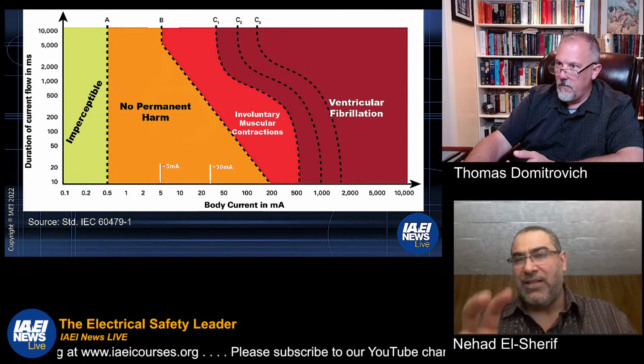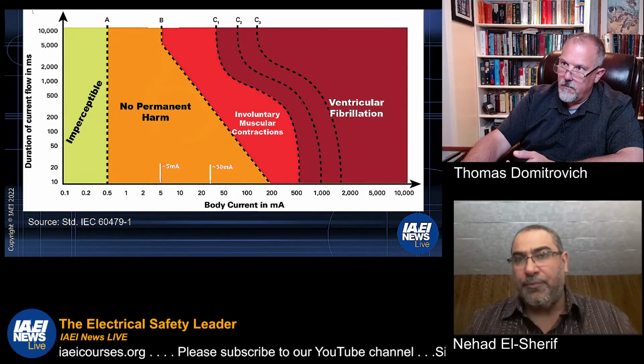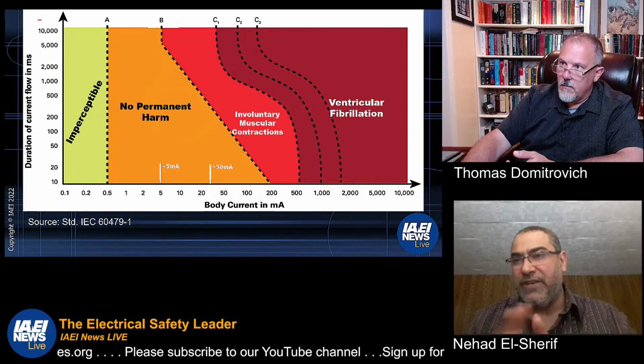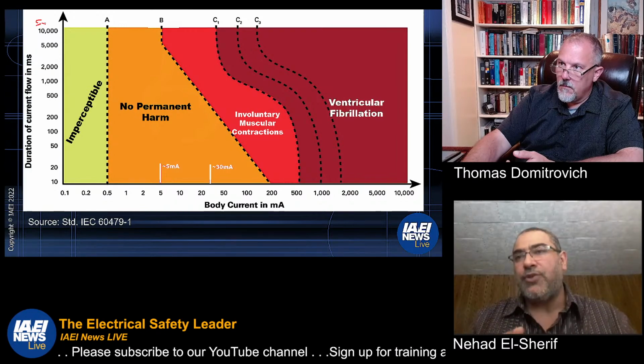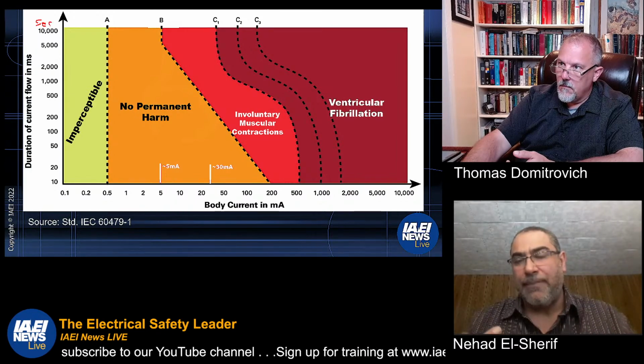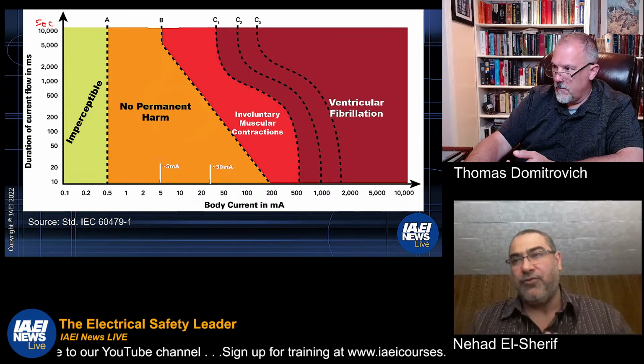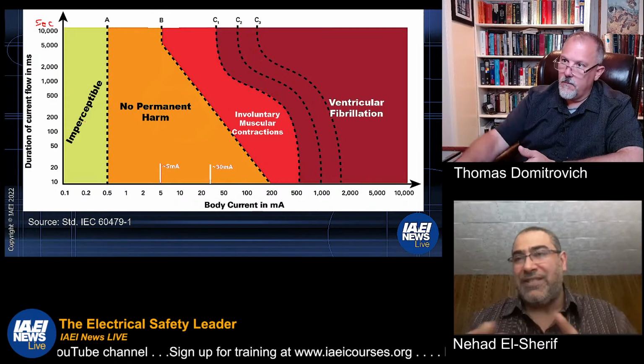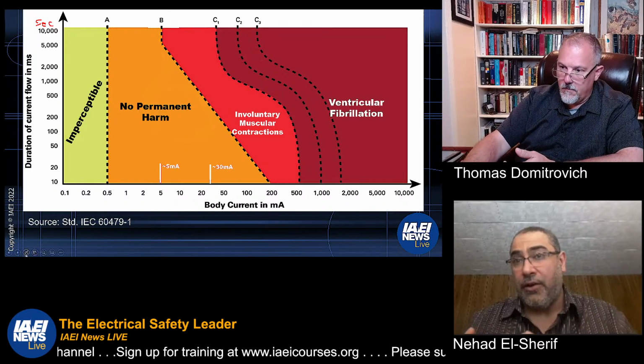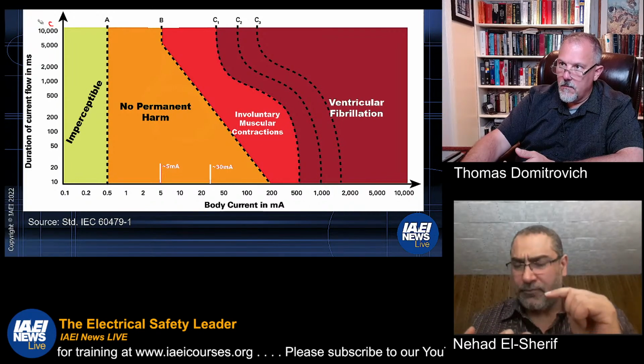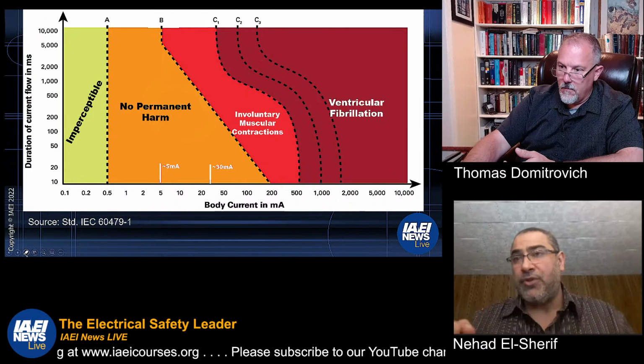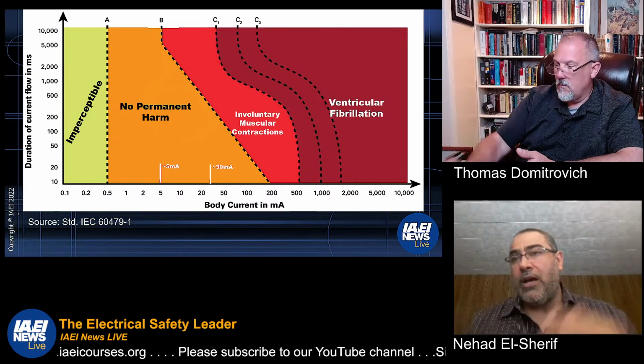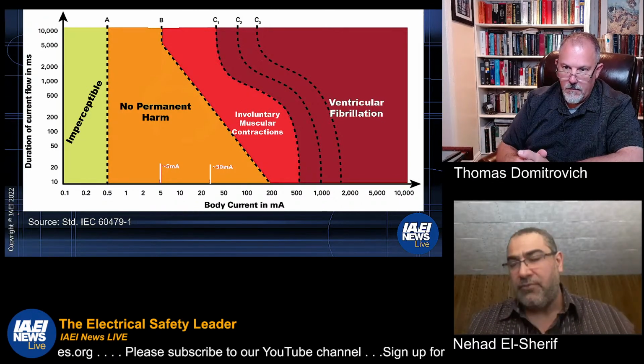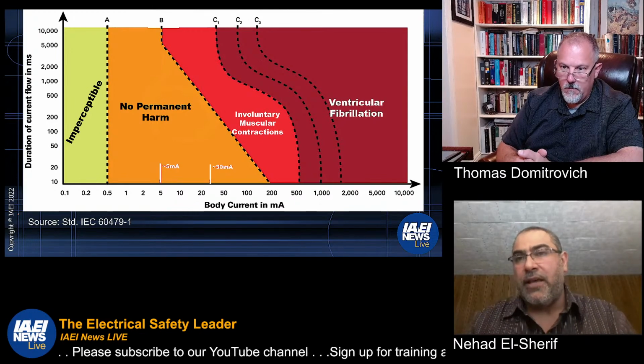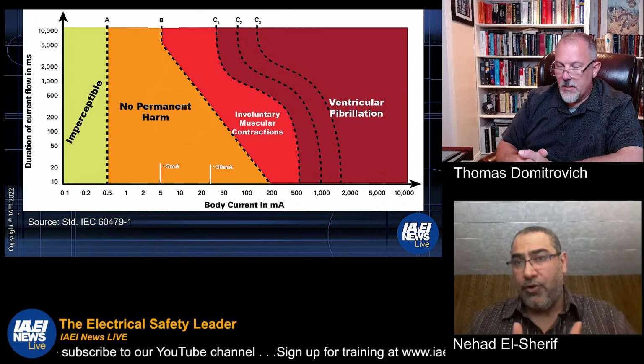So as long as we're in this no permanent harm area, this is kind of where GFCIs try to operate. Yes, you would feel the zap, you'll feel that there was a shock. I'm not saying it's like the green area where you barely feel anything. You still feel the current, but it's in this area. If the current is interrupted, either by a person letting go of the circuit, or by a device, a GFCI in this case, then there will be no permanent harm occurring.